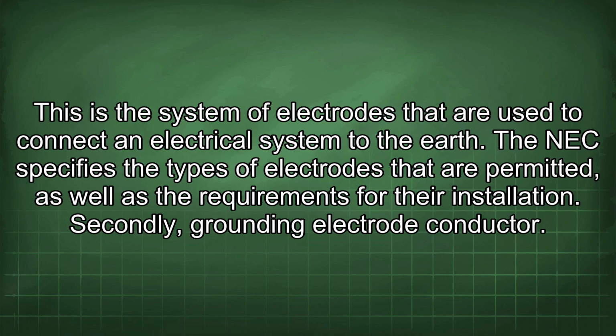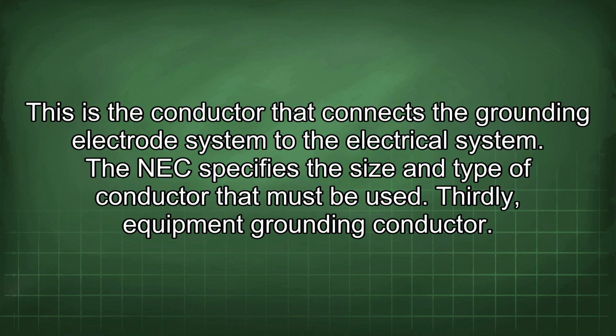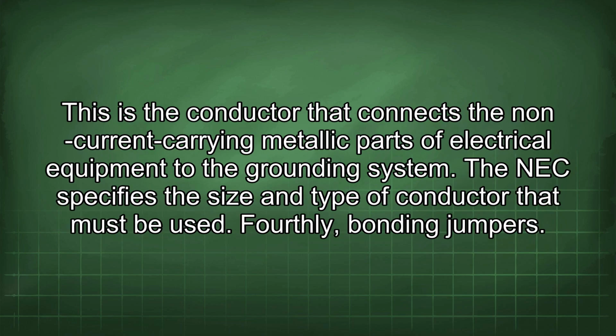Secondly, the grounding electrode conductor. This is the conductor that connects the grounding electrode system to the electrical system; the NEC specifies the size and type of conductor that must be used. Thirdly, the equipment grounding conductor. This is the conductor that connects the non-current carrying metallic parts of electrical equipment to the grounding system; the NEC specifies the size and type of conductor that must be used.